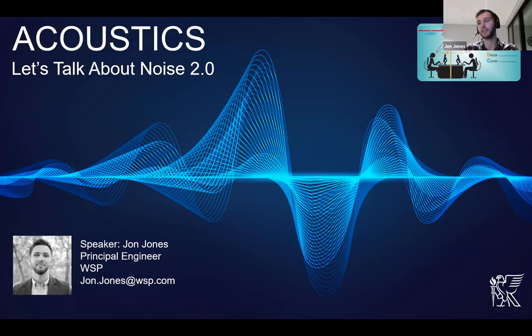The other thing to consider is the length of the attenuator. Again, increasing the length of an attenuator, you get longer airways, you get more acoustic absorption in those channels, and that again increases the performance of the attenuator. That doesn't have so much of an effect on the pressure drop, but there's a trade-off there to be considered. But it comes down to fan selection, and there can be an iterative process there: if a fan is selected at its maximum, the system is designed for a certain total resistance, and you add late in the design an attenuator with a certain amount of resistance, you need to make sure that the fan is capable of dealing with that.